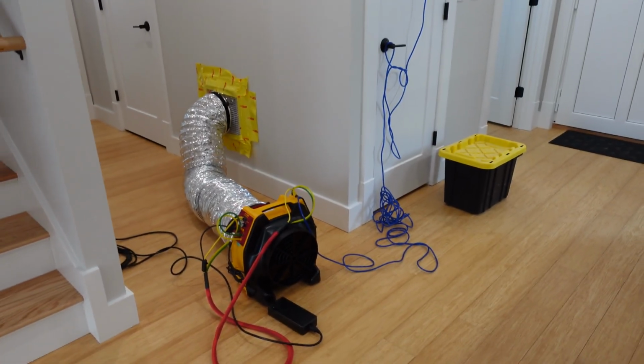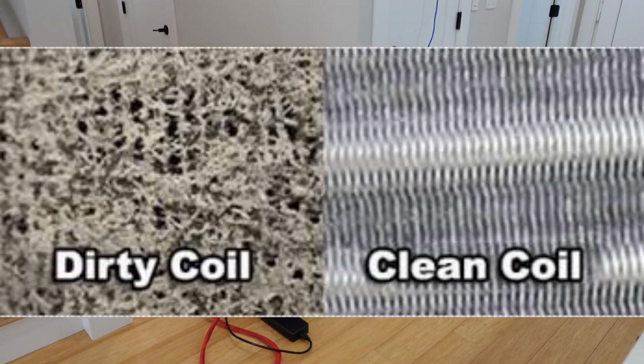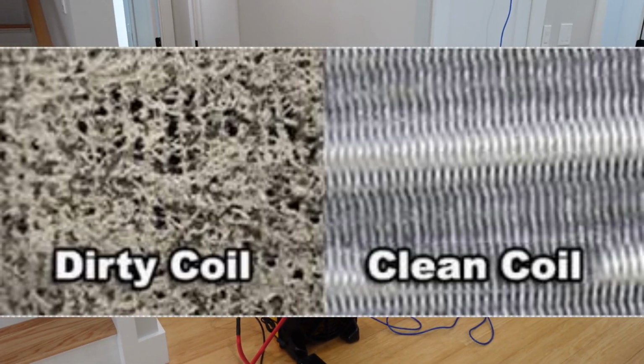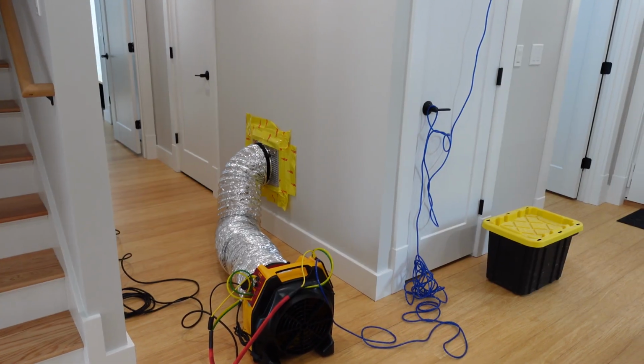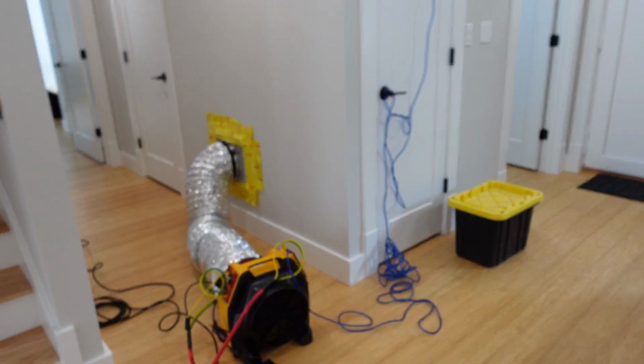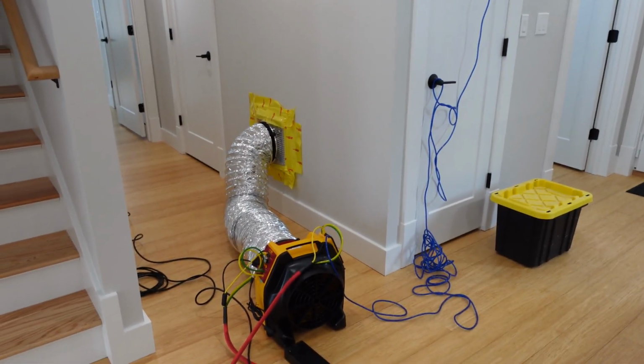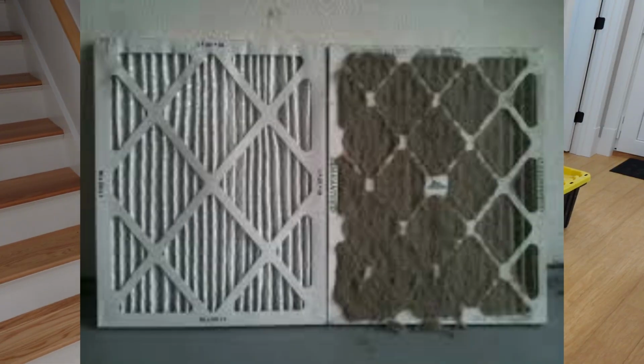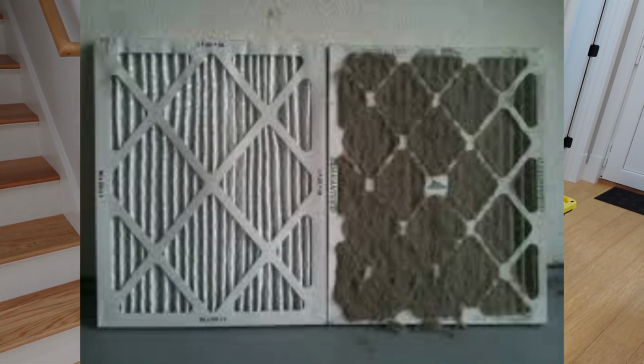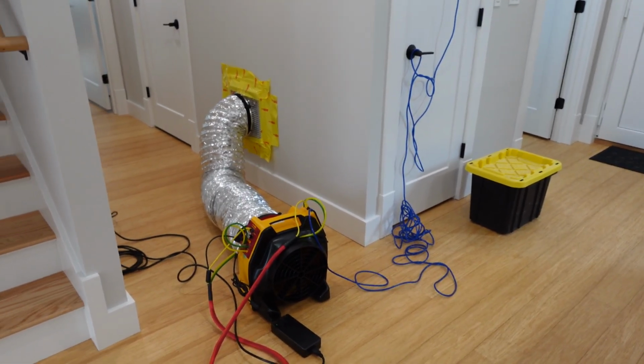If you have a lot of leakage and the cold air return is sucking a lot of that stuff in, and it sticks to the coils in the air conditioning system, that's going to create a lot more static pressure build up over time. It's going to clog the filters. That static pressure is then going to increase the strain on the blower motor and could burn it out.